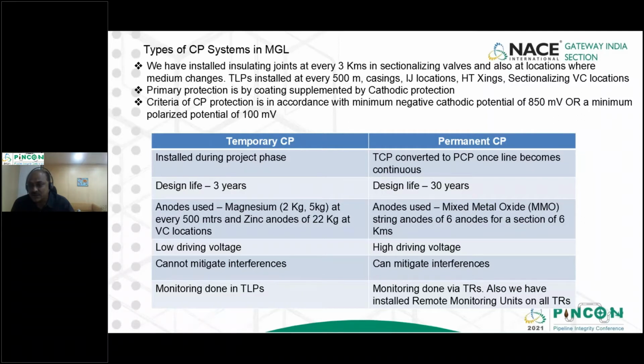Because during the project phase, we are not able to continuously lay pipeline. There are certain sections which remain disconnected. So we have a temporary cathodic protection during the initial project stage. The design life for the temporary cathodic protection is 3 years, while for permanent cathodic protection it is 30 years.